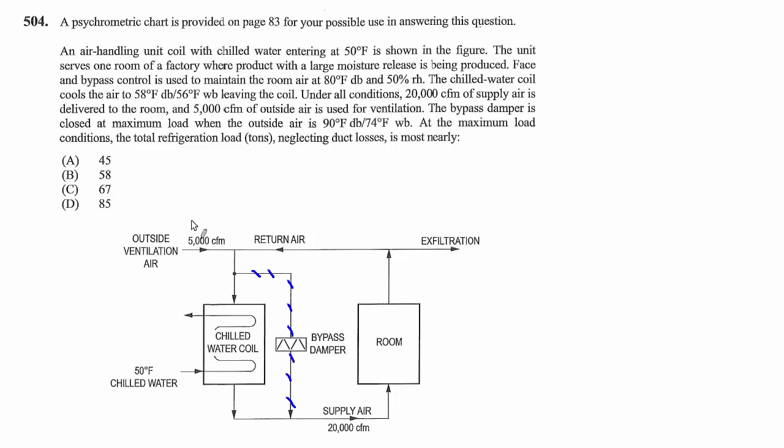The exhaust and outside air stuff does need to be taken into consideration. Let's put some of the numbers they gave us onto this diagram. The stuff that's coming back from the room—the return air—we know it has a temperature of 80°F and a relative humidity of 50%. We also know 5,000 CFM of outside air is being introduced, so of the 20,000 that was supplied, 5,000 had to have been exhausted in order to allow for that outside air to be introduced. So this return air volume is only 15,000 CFM.